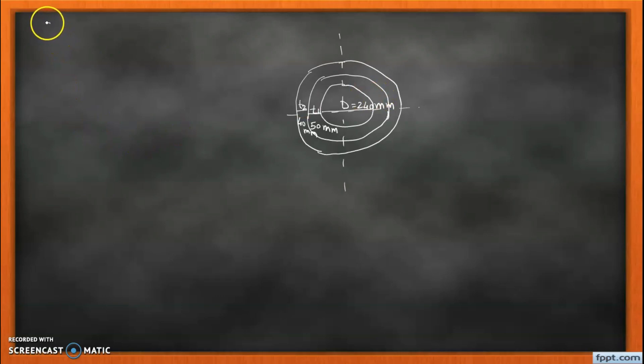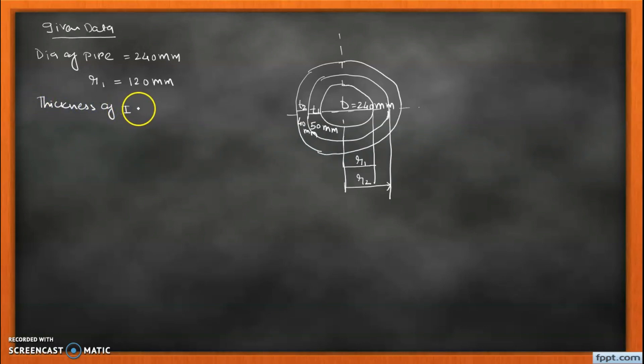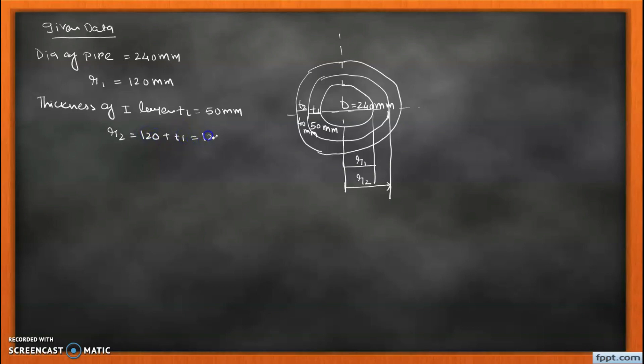Writing down the given data: the diameter of the pipe is 240 millimeters, which means radius r1 is 120 millimeters. The thickness of the first insulation layer t1 is 50 millimeters, so r2 = r1 + t1 = 120 + 50 = 170 millimeters.